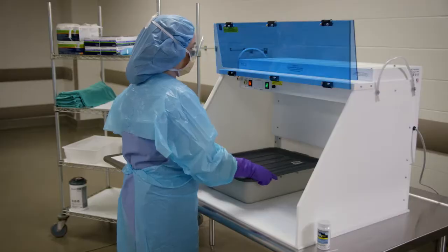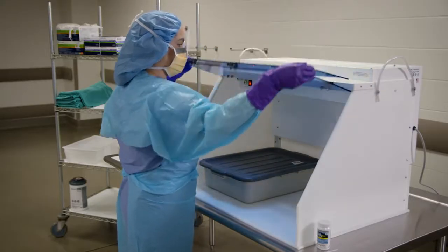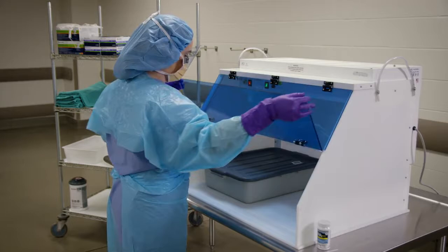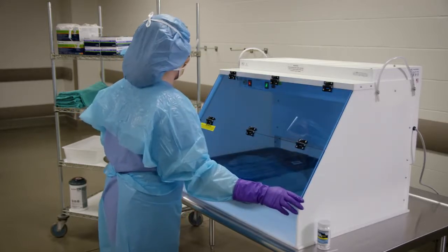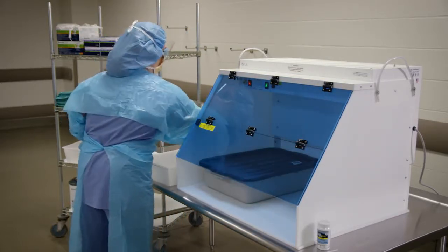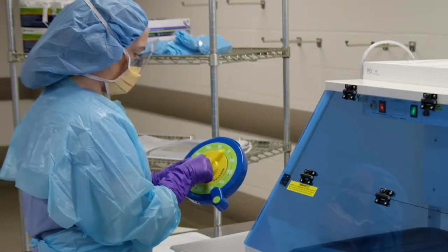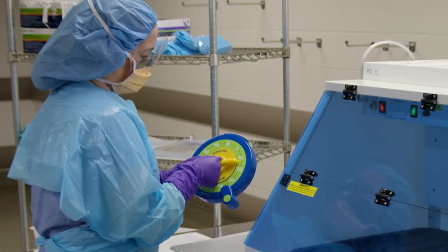In my view, we should be trying to move away from the use of manual processes for high-level disinfection. One of the reasons for that is that it's very, very difficult to do manual high-level disinfection correctly. You have to maintain the temperature of the high-level disinfectant in that basin for the entire time, or the disinfectant won't work. And you have to make sure that you're exposing the scope to that disinfectant for the appropriate amount of time. Now, if you expose it for too short of a time, a quick dunk in that bath of high-level disinfectant, that won't work.